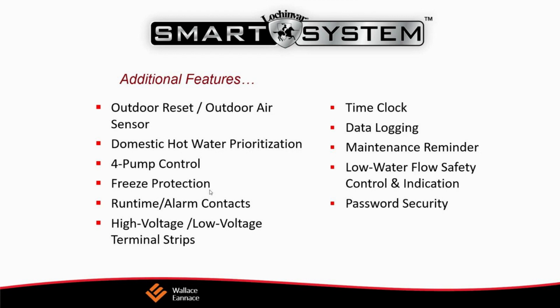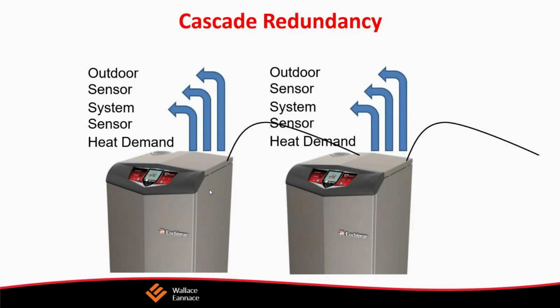And they actually show it to you as a graphic so you can see exactly what temperatures are operating and where. These systems have a lot of benefits to the smart system. It comes with outdoor reset, and all their boilers come stock with an outdoor air sensor. As an option, you can get a wireless outdoor air sensor. It has domestic hot water prioritization. You can control up to 4 pumps.